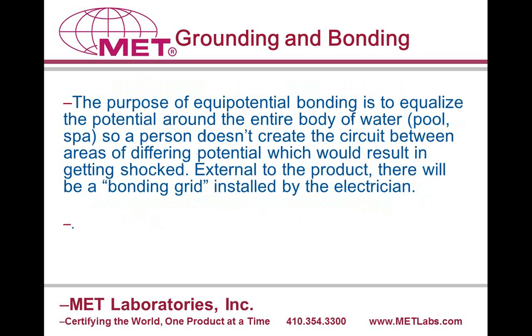Please read this too. The critical point is that your product is permanently connected. So your electrician will have connected all of the metal to a grid. If it's cord connected, you have to require through your instructions that the customer ground the plug. Again, we have equipotential bonding to equalize the potential around the entire body of water so that the person doesn't create a circuit between areas of differing potential, which could result in getting shocked. That's what we're concerned about, is making sure that a person doesn't get shocked.